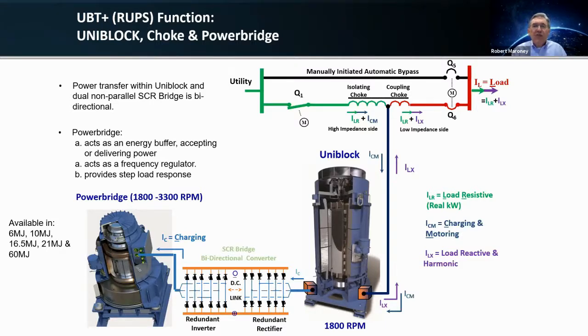And that is we can actually use the flywheel to not only deliver instantaneous ride-through power, but in a microgrid application, I can actually dial the flywheel speed down to around 2,400 RPM if we want to. And I can actually use it as a shock absorber in a microgrid application. So think of this system as the utility to load as a microgrid bus. And you've got photovoltaics, wind generation running, and utilities serving power, and somebody shuts off a motor in the facility quickly. Because, as you know, the microgrid equipment, photovoltaics and wind generation, don't stop producing power immediately like the motor being shut off does.